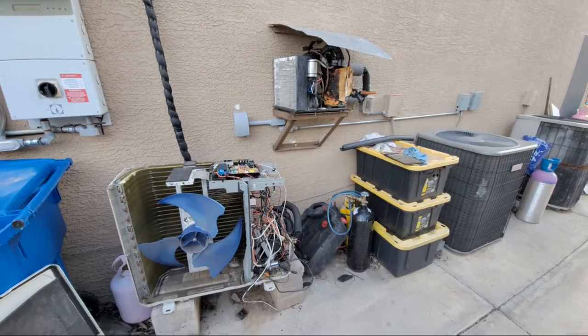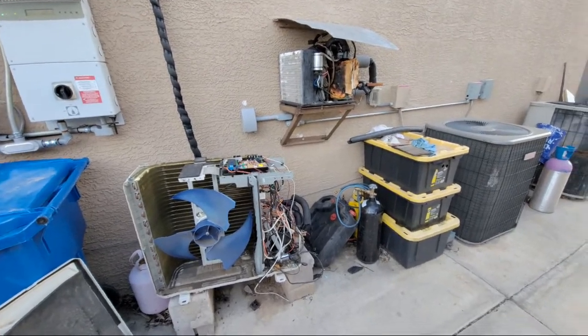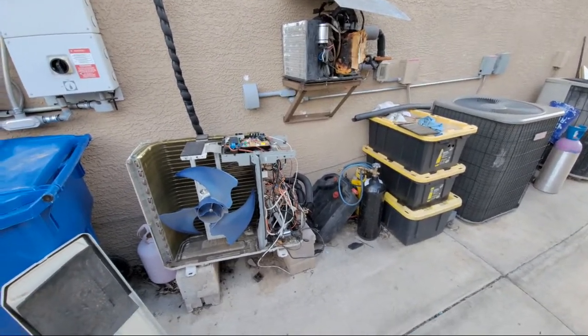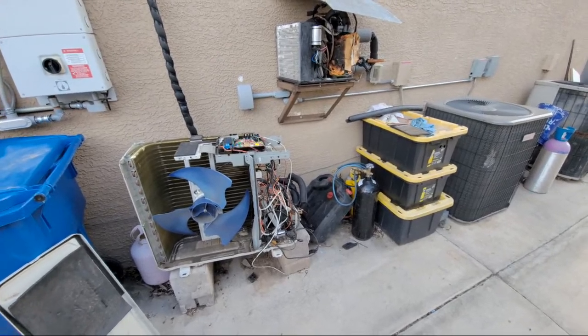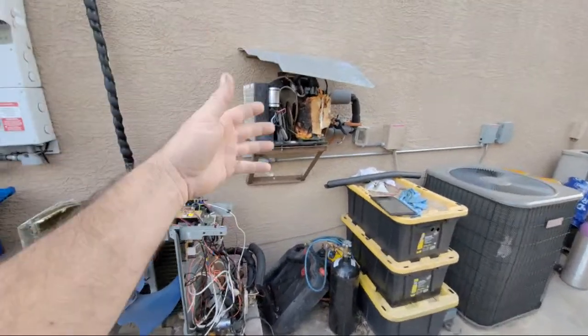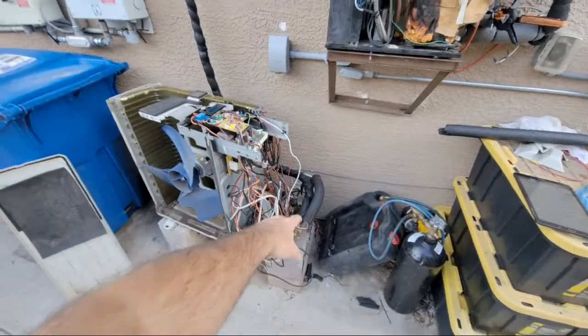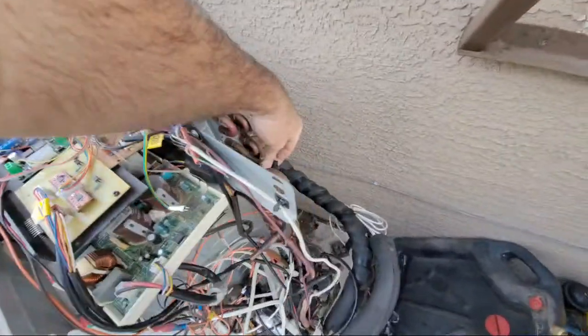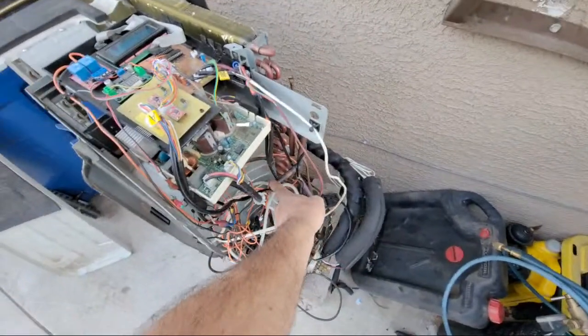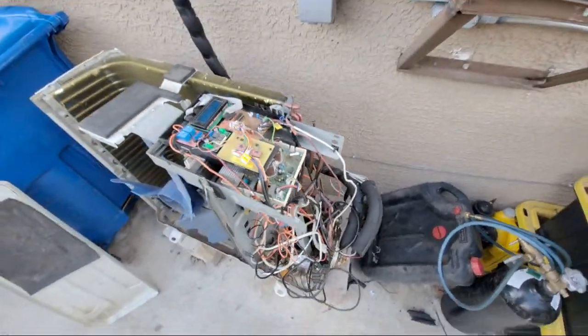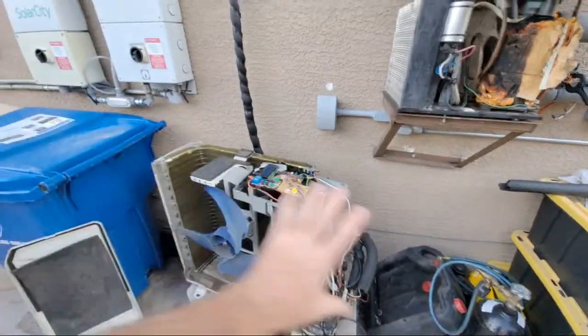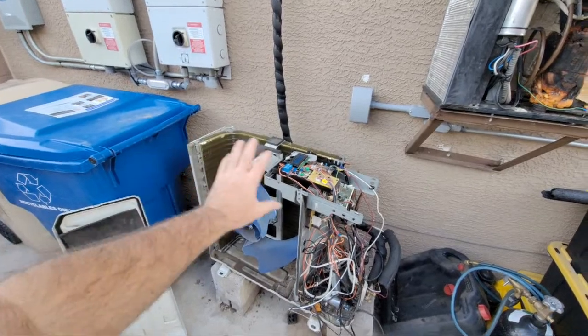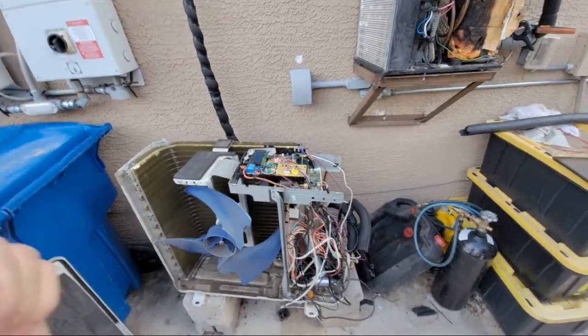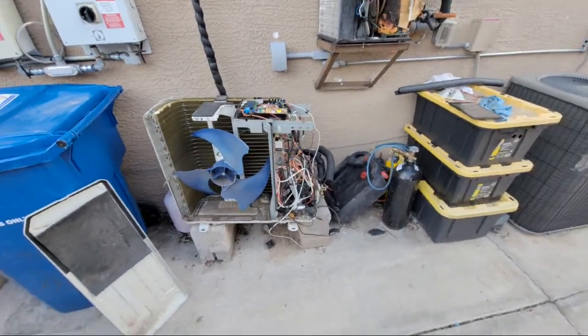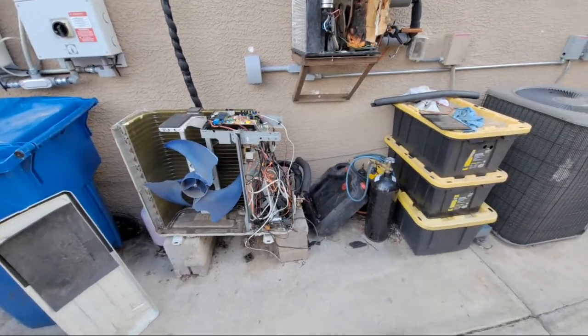And my friend's like, what's up with that? So I'm telling him, your mindset is like, there's no problem. I've had condensed liquid feed in the expansion valve. I had a thermistor here, and then one on the suction line, disconnected right now. One inside was able to adjust the evaporator superheat perfectly, and that all ran perfect. It's just an oversight of how it was going to perform for heating.